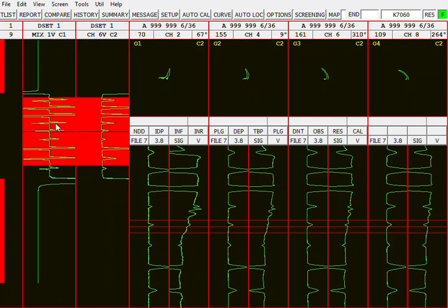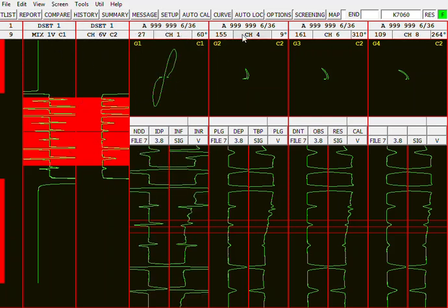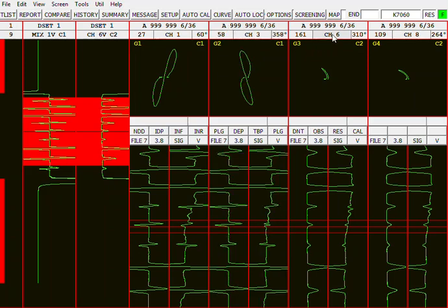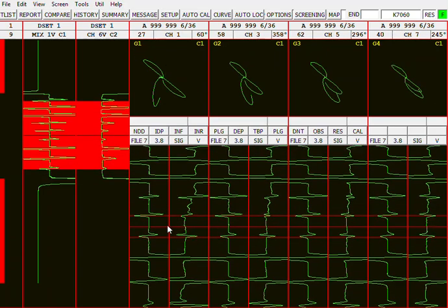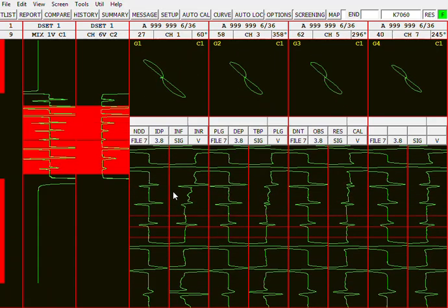Okay, so now we talked about the vertical strip charts, the different channels we're going to watch. Now we'll just get over, let's see, we'll put 1, 3, 5, 7 back up here. The way data analysis, or data evaluation, is done is you're doing a lot of looking at the phases of the different indications. So again, I can display one Lissajous and one expanded strip chart, or I can put 3 or 4. Same thing with the strip charts, I can put as many as I want. But when you start to put too many things in your display, it gets kind of busy. And then you may be looking all over, and you might miss one of the charts or the displays that has some flaw information in it.